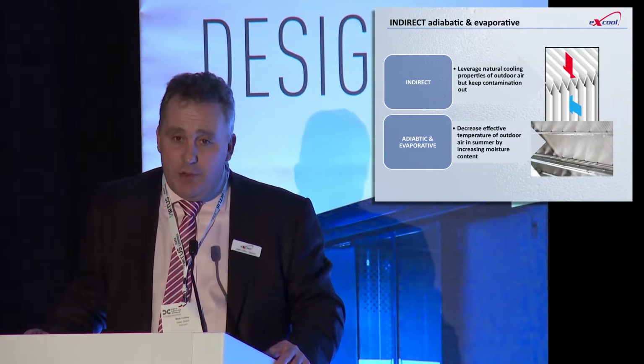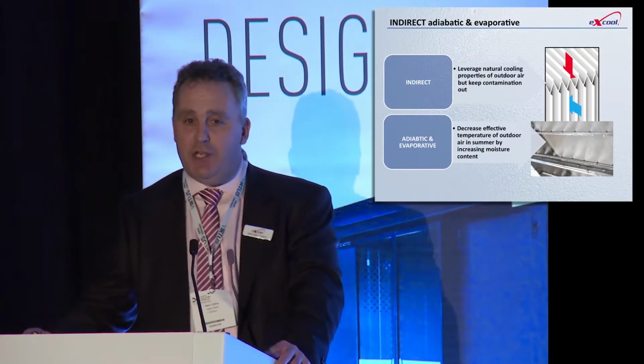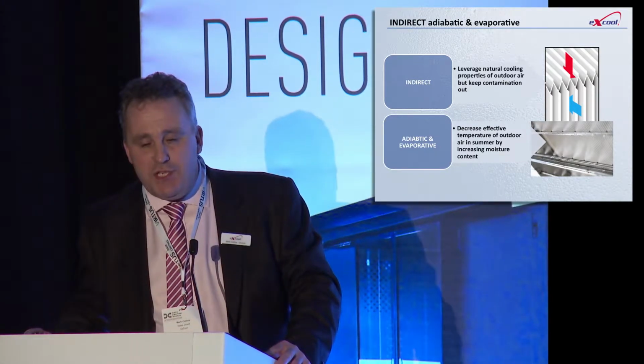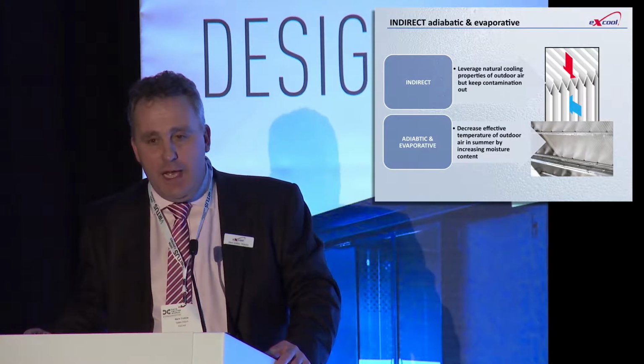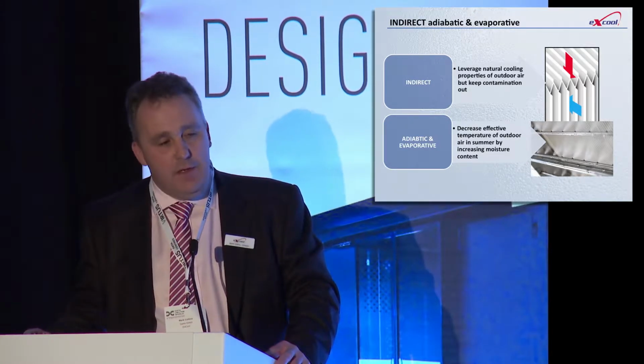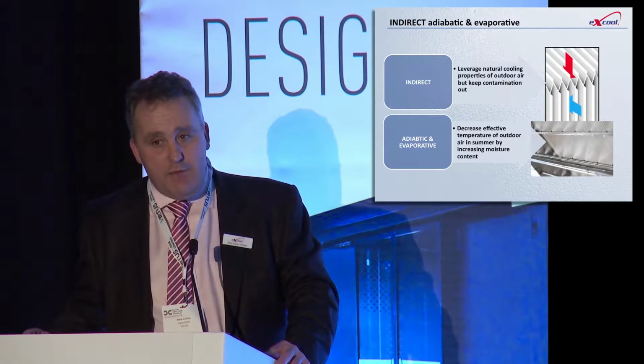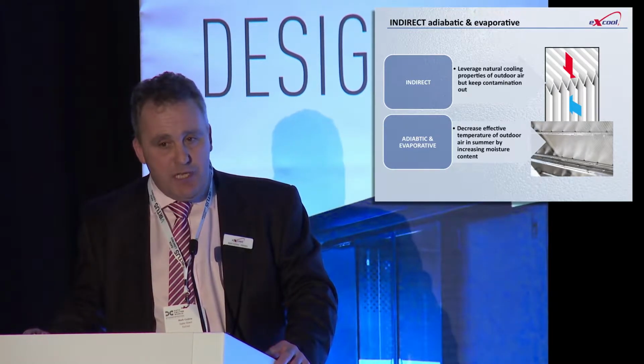Now, in the winter, when the outdoor air temperature might be at 10 degrees C, that's a fairly straightforward thing to do. We're passing air through one side of a heat exchanger, and we're using that to remove the heat from the data center on the other side of that heat exchanger. The two air streams never meet.